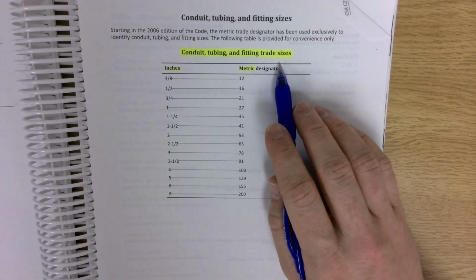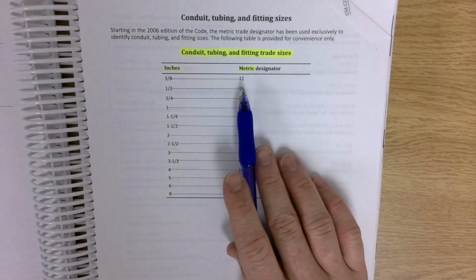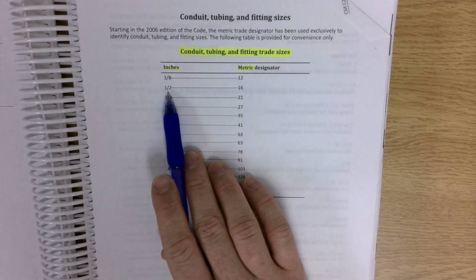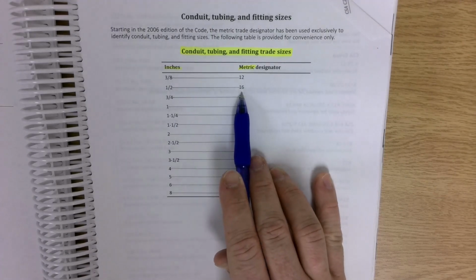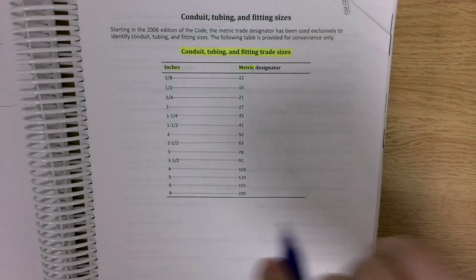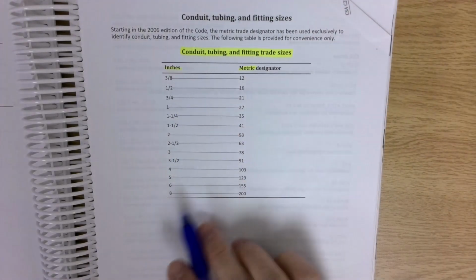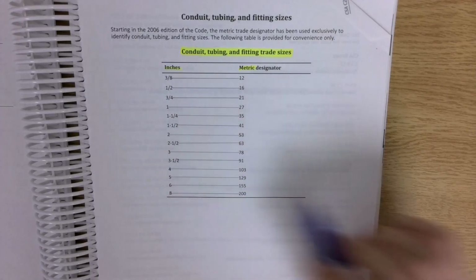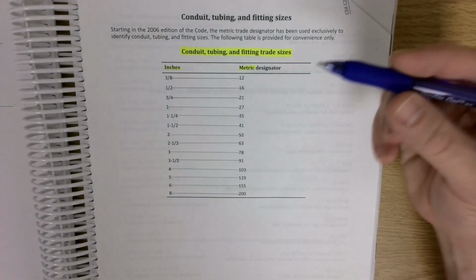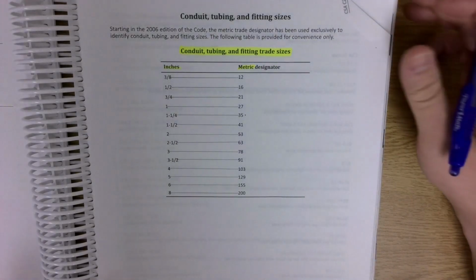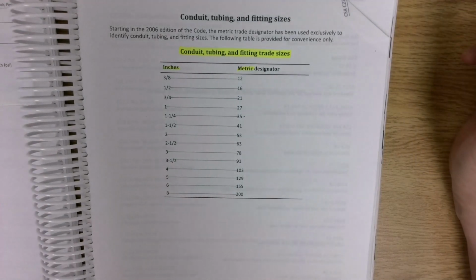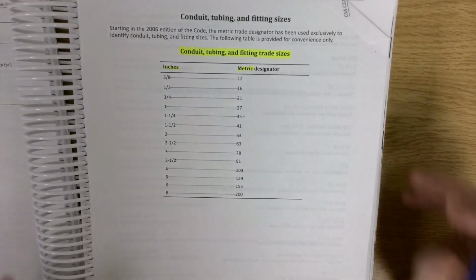If you have a smartphone, maybe you'd wonder why this exists, but it's there if you need it. There's also conduit tubing and fitting trade sizes. So in the codebook, everything will be in metric, as far as I know. So if you're talking about half-inch conduit, the codebook calls it trade size conduit 16. So I have this page saved because I've used inches for all my conduit tubing and fitting trade sizes. So when the codebook is talking about rules for trade size 35 conduit, I can't picture what that is. And a good thing that helps you understand what the codebook is talking about is relating it to field experience.